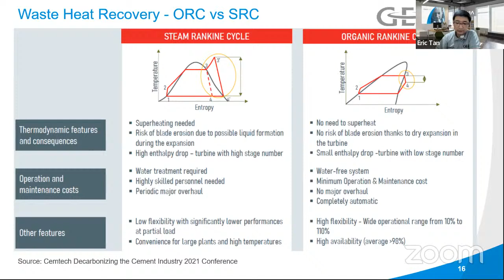Then the last, about other features between the steam cycle and ORC: the steam cycle has low flexibility, which gives significantly low performance at partial load. But in the case of ORC, as I mentioned earlier, they are highly flexible, where we can operate widely from 10% up to 110% range. Then of course, the steam cycle has some pros and cons, and in this case, it is convenient for larger plants at a higher temperature. For the ORC, one of the things that we highlight here is the high availability. On average, we are talking about more than 98%.